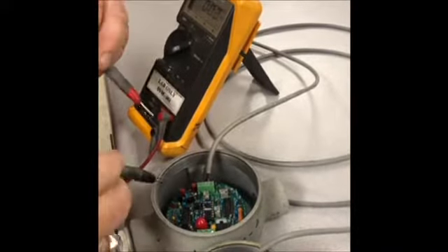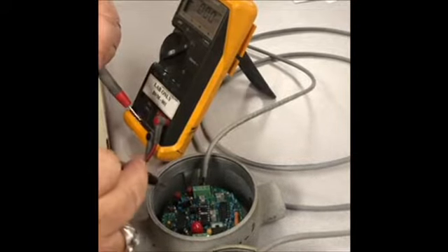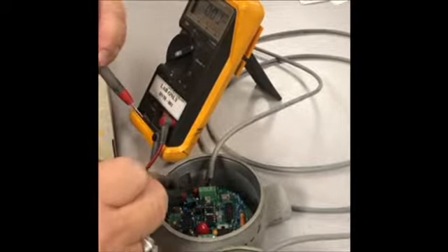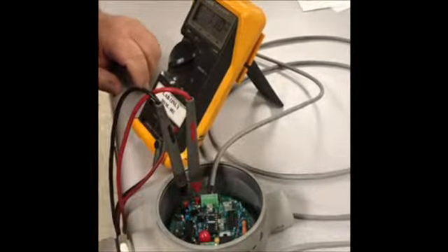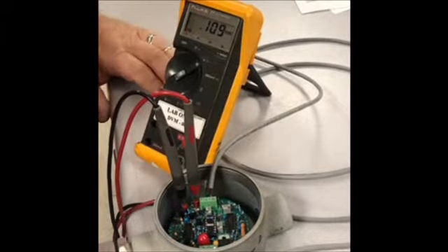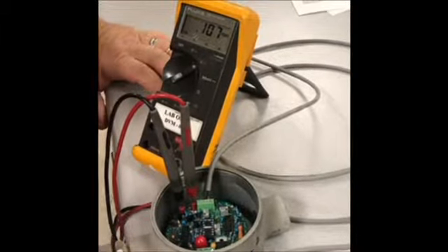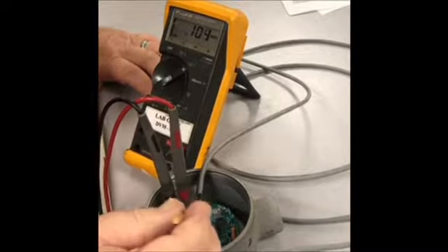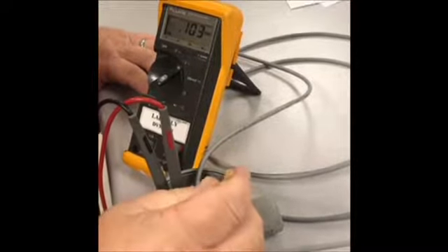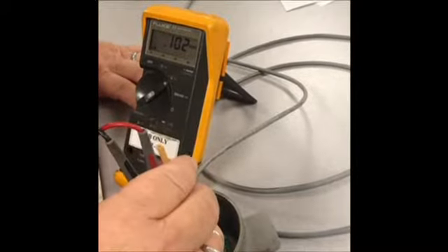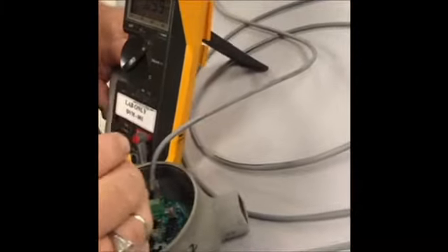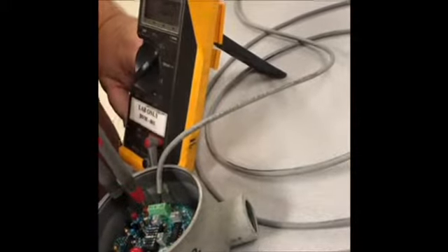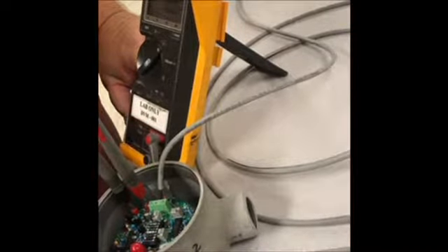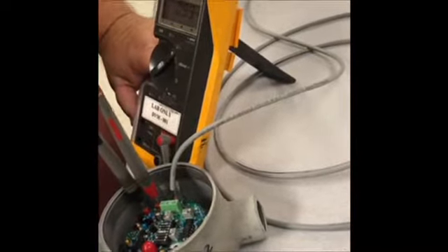At that time, we're going to measure the output at TP1 and TP2, these two test point sockets. These sockets will hold the probes from the voltmeter in there by themselves. It should be 0.10 volts at 0. You can see that it's slightly above that. I'm going to use this screwdriver to turn this potentiometer slightly down till I get 0.1 volts approximately. 0.102, 0.101 is fine. We really want 0.1 volts.